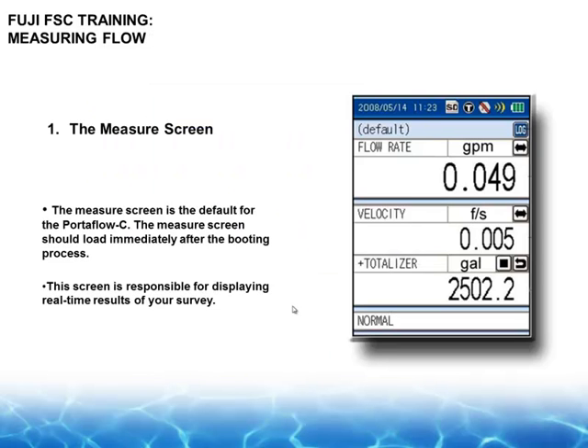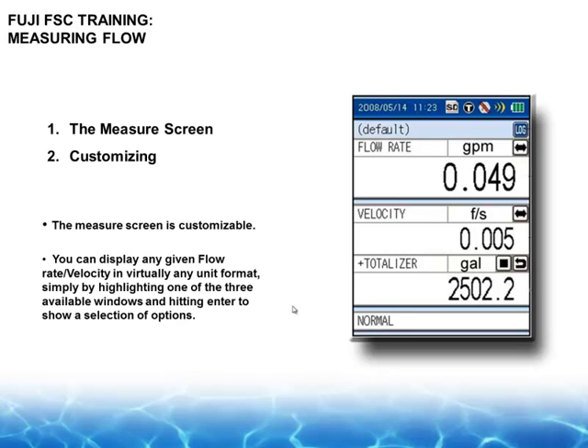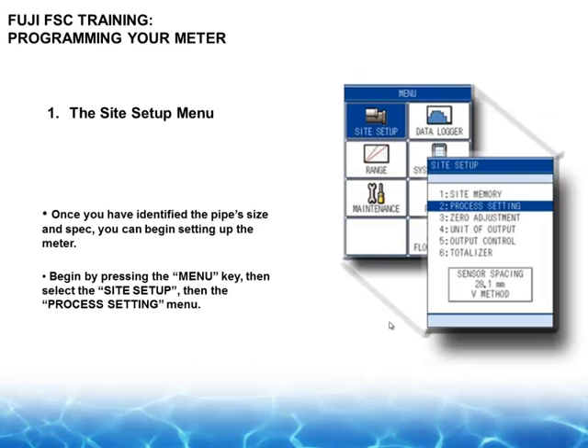The device has a GUI interface screen. The measurement screen is the pop-up when you turn the meter on. And basically you have the ability to customize it. The top line, we traditionally make it read flow rate, velocity, and totalization, but there are other parameters. You can move it around to your preferences there. You can program anything that you want from the face right here. And then the bottom notation there, after you're up and running, says that everything's ready to go for your application, so everything's in a normal situation.